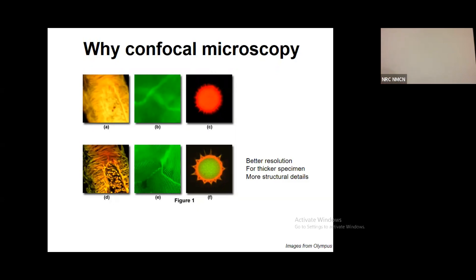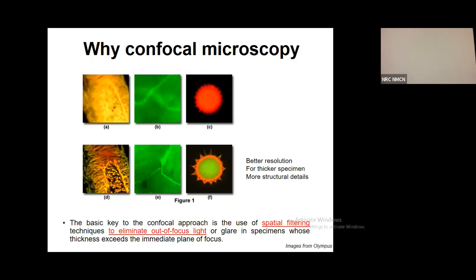Confocal microscopy can definitely provide more structural details. How does confocal do it? It basically uses certain restrictions or spatial filters to reject out-of-focus light. If you have all the light coming together to the detector, images will be more illuminated but you will lose resolution because of less contrast. We can improve contrast by rejecting out-of-focus light - that is the basis of confocal microscopy.